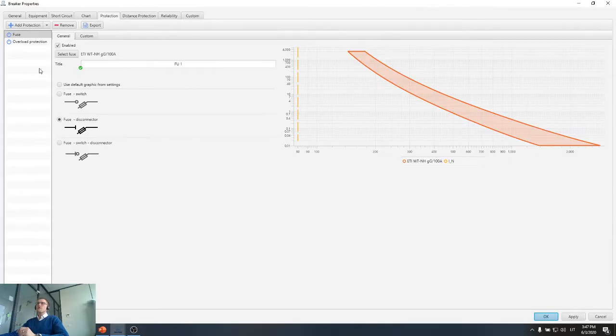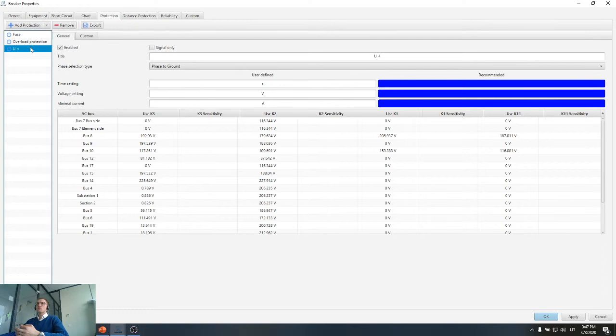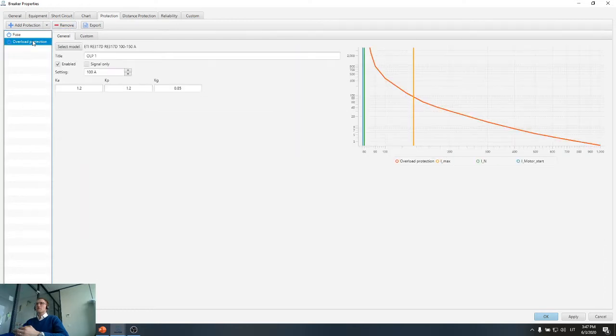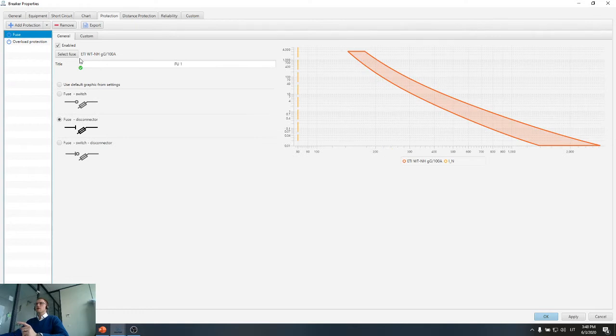It is very easy. On the left side you have a broad list of different protection devices that you can add, and just by adding protection devices from the list, let's say I can select a fuse and I can select overload protection. If I need, I can also select ground fault protection or voltage protection, so I can select as many protection devices as I want in this list here. So now I selected two protection devices, fuse. I have already shown how to select the fuse.